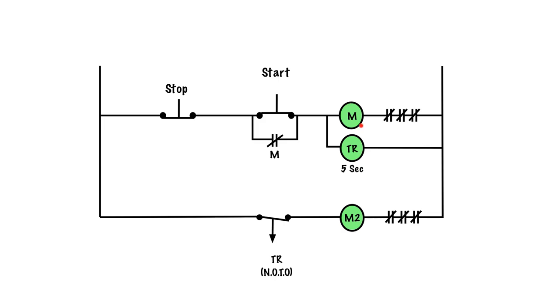When I press start, the M coil energizes, the M contacts close to form the hold-in circuit, the TDR coil energizes, those contacts close, and M2 energizes. The timing function has no role at this point — the moment I hit start, M energizes, TDR energizes, and M2 energizes all at the same time. When I release the start button, everything is held in by the hold-in contact, which provides a parallel path keeping everything energized and the contacts closed.